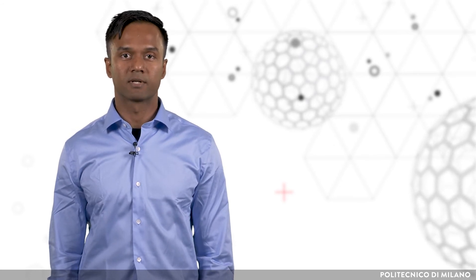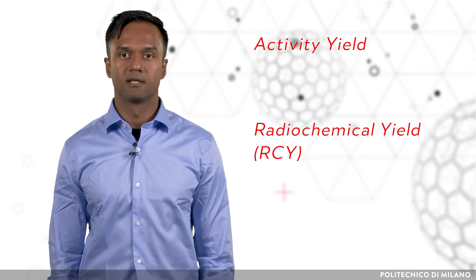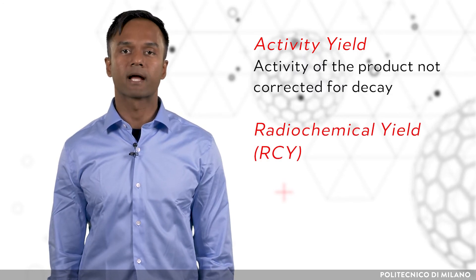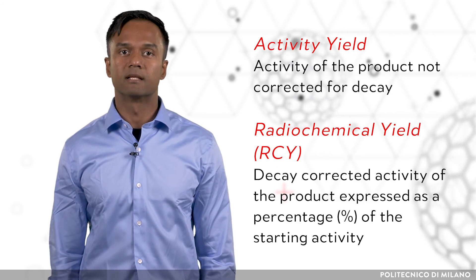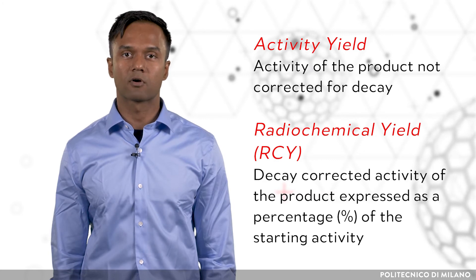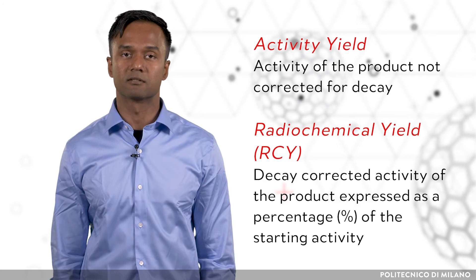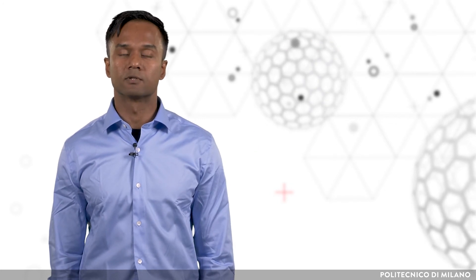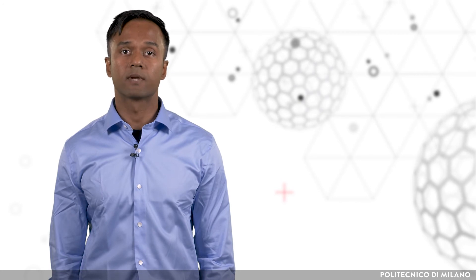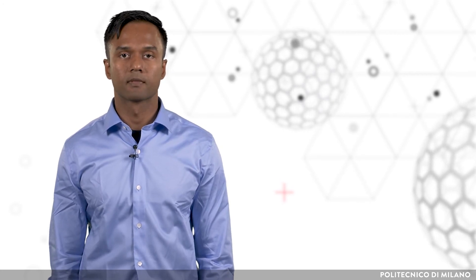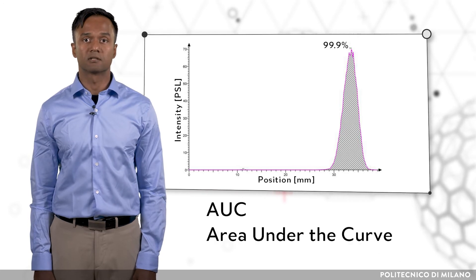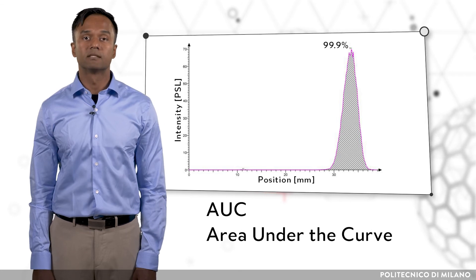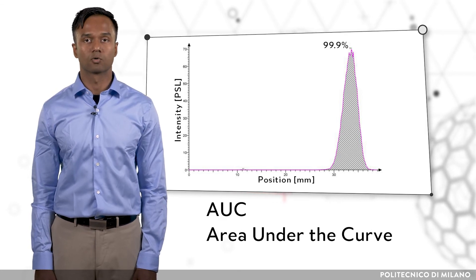The radiotracer yield can be expressed as the activity yield and radiochemical yield. The activity yield is the amount of radioactive product obtained, which is not corrected for decay, whereas the radiochemical yield is calculated from the decay-corrected activity of the product expressed as a percentage of the starting material. With regards to purity, it is important to assess the absence of other compounds — chemical purity — as well as the absence of other radiochemical compounds — radiochemical purity. The radiochemical purity is determined by ITLC and RadioHPLC from the integrated area under the curve (AUC) of the desired compound, expressed as a percentage with respect to the total area under all peaks.